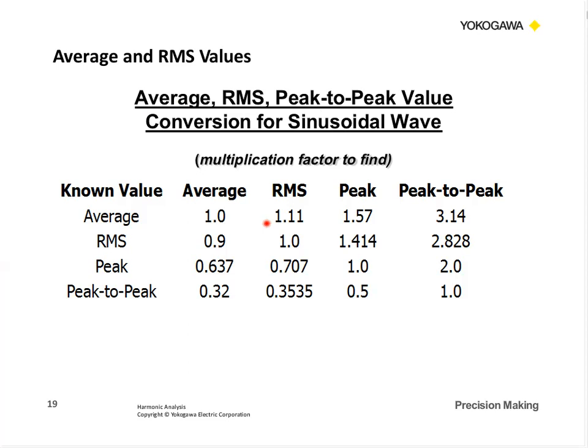And so if we have an average responding meter, like a lot of meters are just average responding, some mechanical meters, we have a multiplier of 1.11, and on the mechanical type instruments, this was just a scale multiplier of 1.11. We do use it in some of the electronic instruments, to get that average to RMS value. So it does come up once in a while. And of course, we know our peak and our peak-to-peak values.